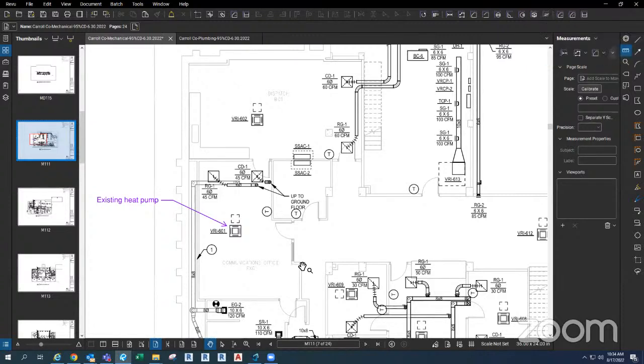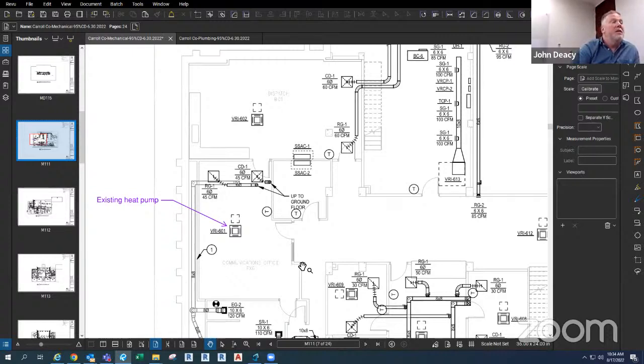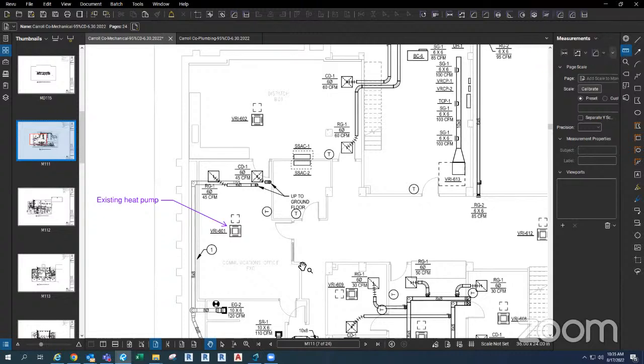That's a good question, Joe or Ryan, I don't know if you want that. I can probably let Ryan speak to that, but I'd assume you'd want it to be. If that system is on the VRF system, then the whole VRF system serving this floor, since it's all part of the same system, would need to be on emergency power, unless you do a separate heat pump system just for this communication office, its own separate system.